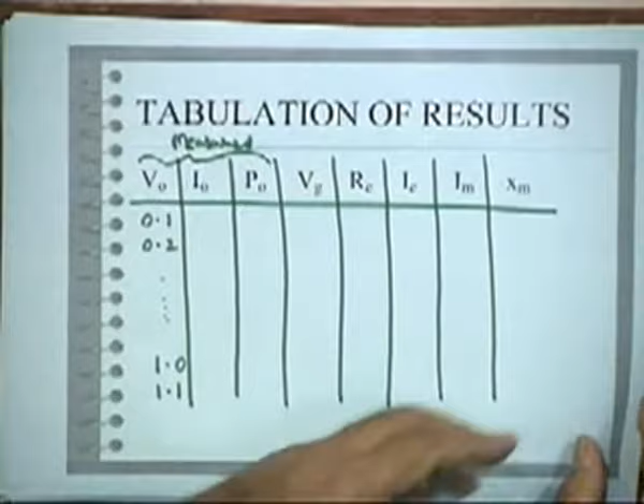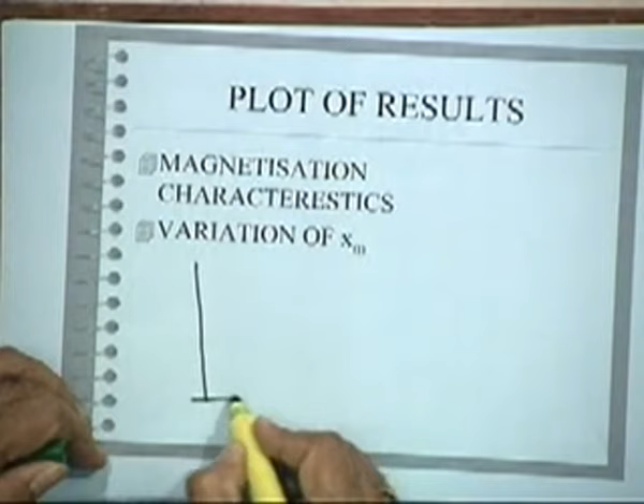You are interested to know what is the magnetization characteristics of the motor, because the magnetizing reactance is not necessarily constant. It depends upon the operating air gap flux, which depends upon the voltage, and you are interested to find out what is the variation of magnetizing reactance, because our whole concern is that they are not really constant. So, it will depend upon the operating voltage and the operating flux. So, what you will plot is the air gap voltage versus Im, and which is not linear. It will be linear initially, but it will go like this.